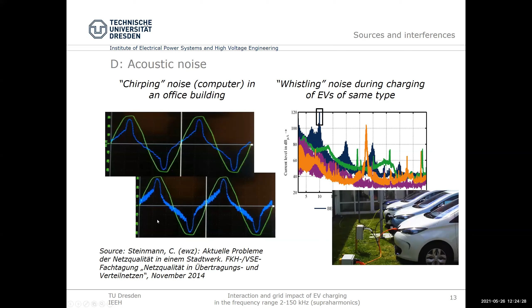This has been observed in the interaction of two UPS systems, shown on the left side. You can see there is sometimes no noise emission at all - no high frequency emission - and then 2 seconds later it's there again, disappears, appears, disappears. This beating can then result in such a chirping noise. It's a quite interesting new phenomenon.